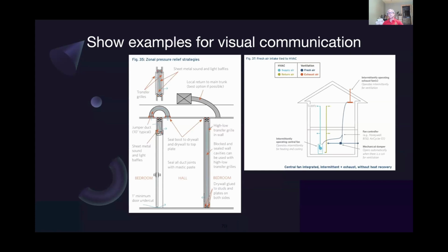Here's some more examples of zonal pressure relief. A lot of programs require that if you've got more than one register in a room, you have to have zonal pressure relief. This could be a jumper duct, this could be a dedicated return, this could be a high-low, but you have to have some sort of pressure relief.